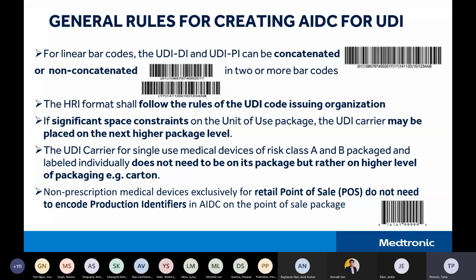Again, the UDI carrier for single-use medical devices of risk class A and B that are packaged and labeled individually does not need to be on its own package, but rather on the higher level of packaging, so maybe just on the carton. Another thing to note is that for non-prescription medical devices that are used for retail, they do not need to have the production identifiers in the AIDC on the packaging. So you can see the representation that we have there. That's only going to give you the DI portion of the barcode.